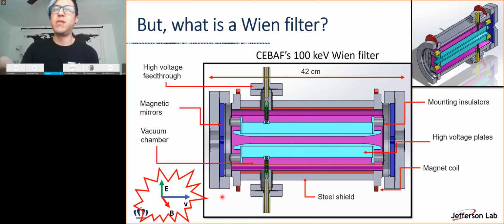And the way we create the magnetic field is by feeding these coils that are a little bit hard to see here, but they're those red regions. They're packed into the device. We put a current through them, and that way we generate a magnetic field in a perpendicular direction to the electric field. These are called window frame coils. We also use these blue sections, called magnetic mirrors, which are used to shape the profile of the magnetic field. We'll see why in a sec. And also there's a steel shield and we have flanges in order to mount everything. So yeah, this is what the Wien filter is all about.